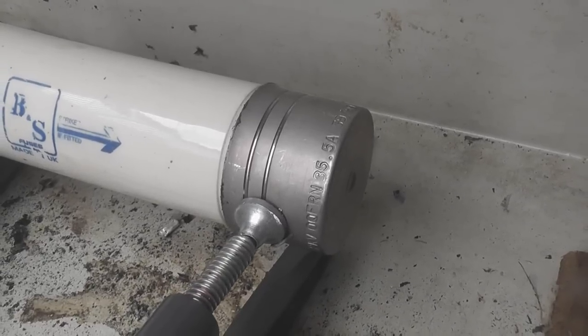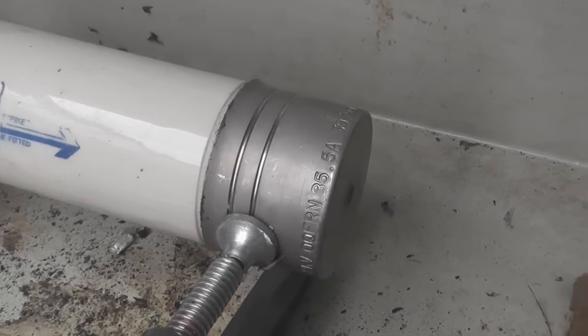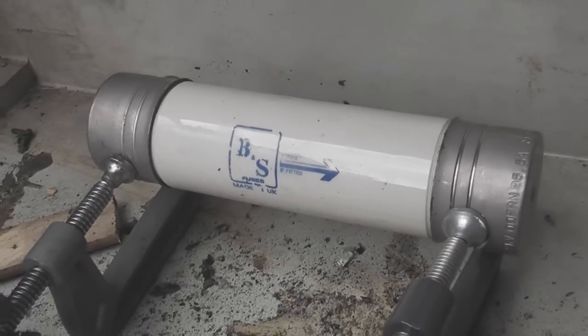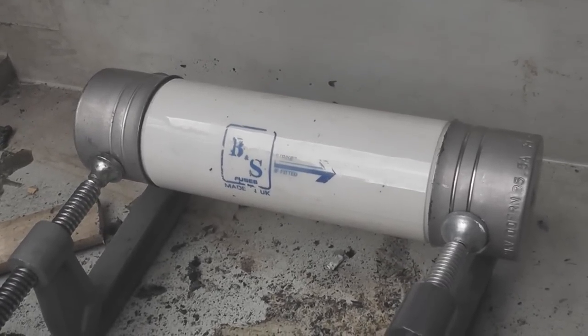I've got here one of these fuses with a striker pin — 35.5 ampere, 11kV fuse. Two fuses had blown, the third one was still okay. So I'll pop this one, see what happens.